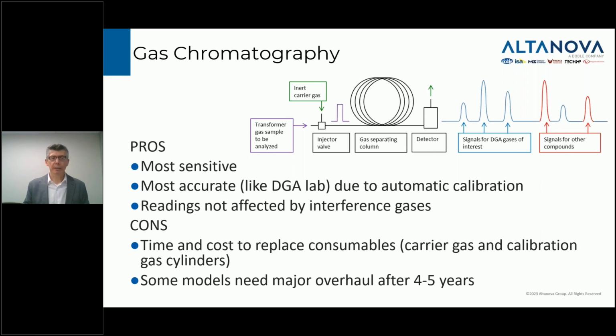They all have an onboard automatic calibration system using calibration gas. And the other nice advantage to chromatography is the readings are not affected by what I'm going to call interference gases or interference compounds. You may or may not know that in transformers, especially older transformers, there can be other gases and compounds present in the oil different from the ones we measure in DGA. There can be, for example, heavier hydrocarbon gases. There can be SF6 occasionally leaking in from a bushing. There can be alcohol, acetone, acids. A whole soup of different things can reside dissolved in the oil.